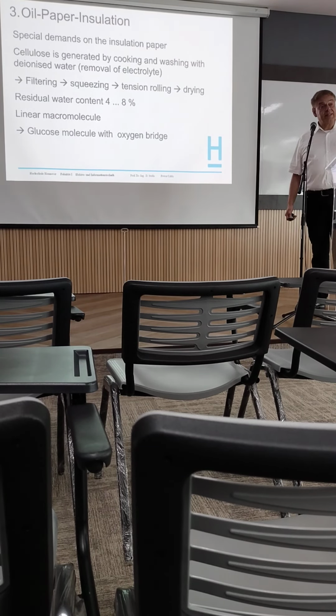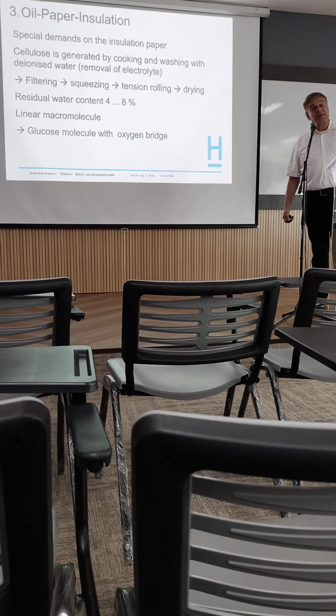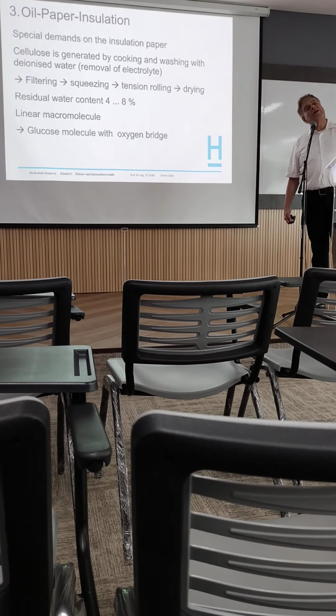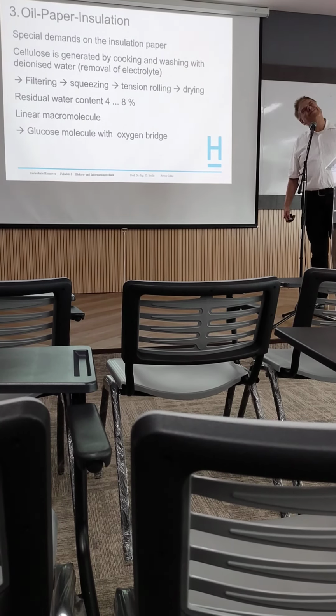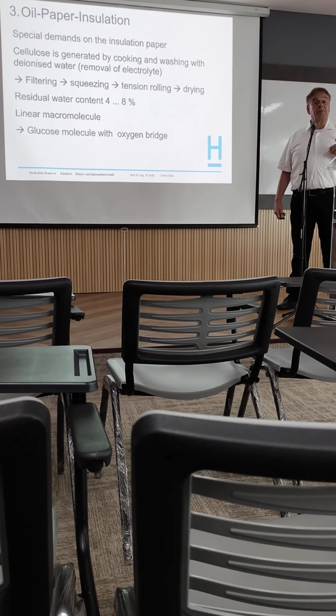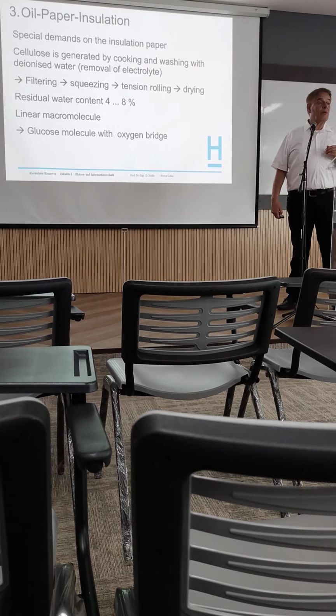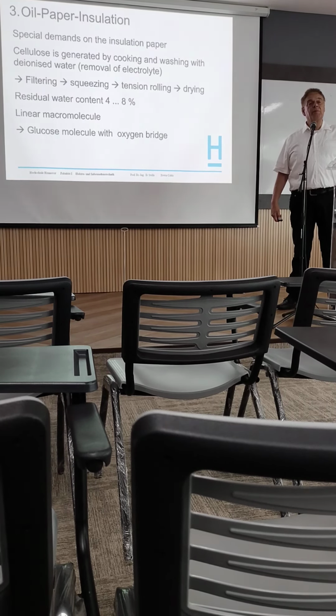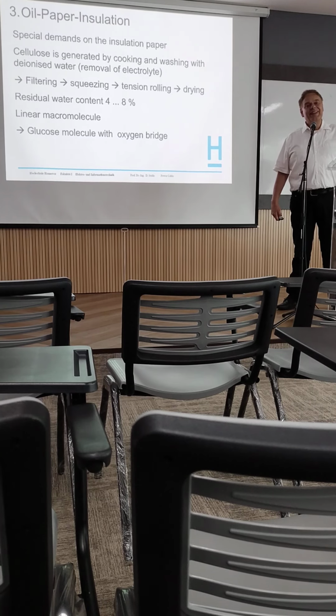Oil paper insulation, as I said already, we will skip, because they are not produced anymore. Maybe there are very few factories that are still producing oil-filled cable in the world. That's actually a problem, because when you work in a company or a distribution company, and there is a failure at an oil cable, there's nobody who will repair the oil cable.